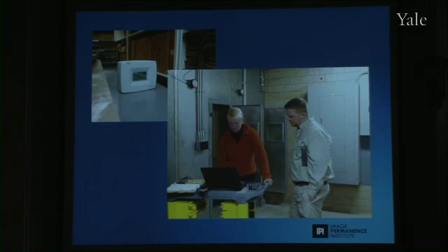standing outside a large, but by no means the largest ever air handler that serves exactly half of the Adams building. The Adams building is the 1934 building on Capitol Hill. It has 12 stack levels. I don't know how many million volumes of books in one giant block square building. And there are two air handlers that serve all those book stacks, a north unit and a south unit. And so we are measuring the amount of energy that is consumed by the north or by the south stack air handler. And what we've been doing recently is turning it off at 8 o'clock at night and turning it on at 6 o'clock in the morning. Shut off, dead, end of story.